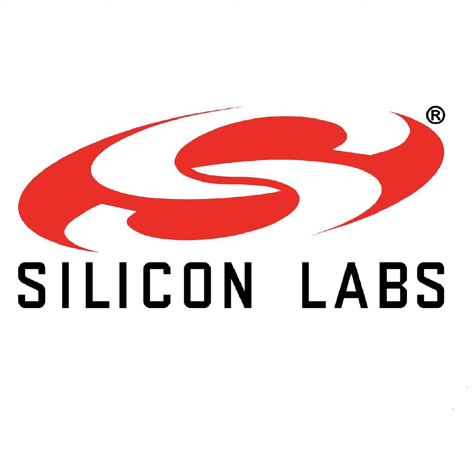And so the way this really usually gets handled is you can't just protect. You basically have to protect and report that there has been some sort of unknown fault. That's a diagnostic. So diagnostics end up being critical. You do protection, but you got to do diagnostics too, or else it's potentially worse than doing nothing. At least if you did nothing, the whole system would blow up and there'd be smoke everywhere, and that's a pretty good indicator that something's gone wrong. When you protect without a diagnostic, you potentially can allow a problem to go unnoticed.